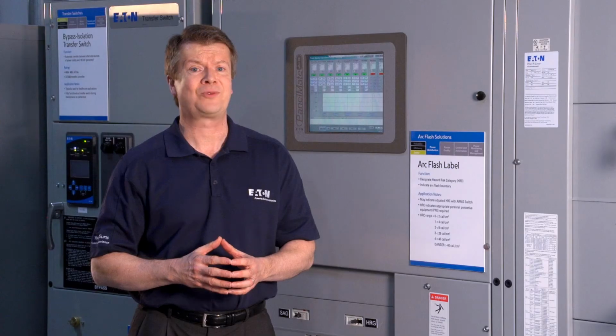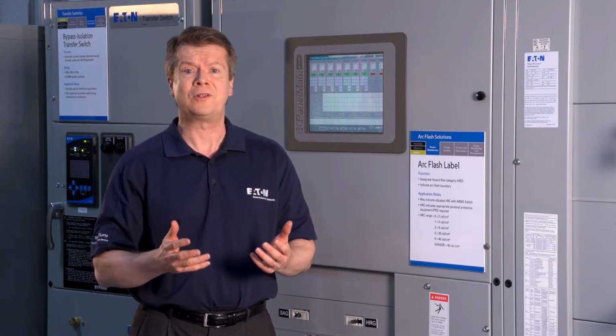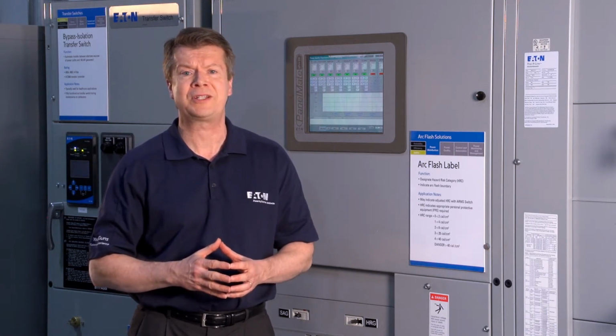About 2,000 arc flash incidents are reported each year, and as you can imagine, it is likely the actual number is significantly higher as workers are embarrassed or fearful of losing their jobs if they report a near-miss incident involving an arc flash. Arc flash energy is measured in calories per centimeter squared.